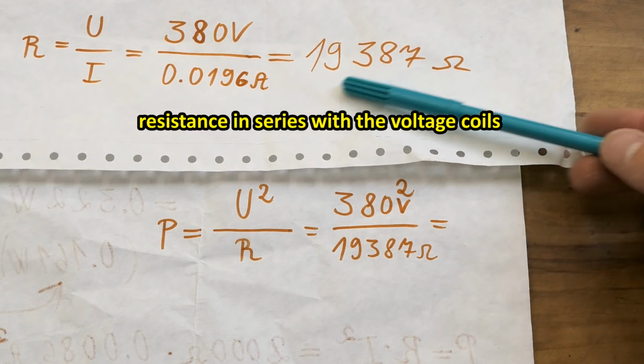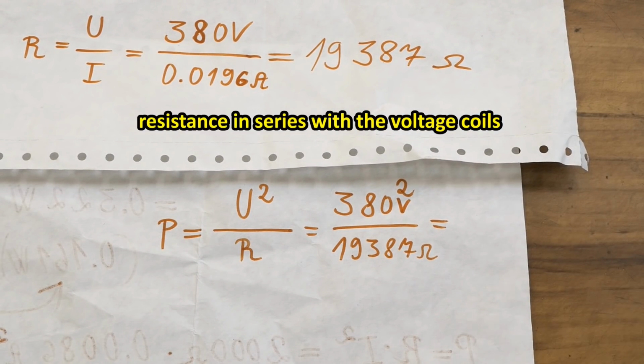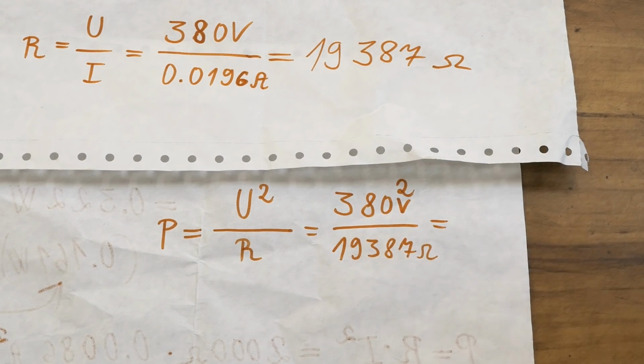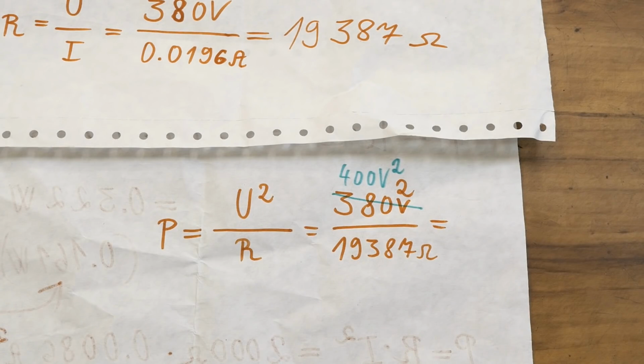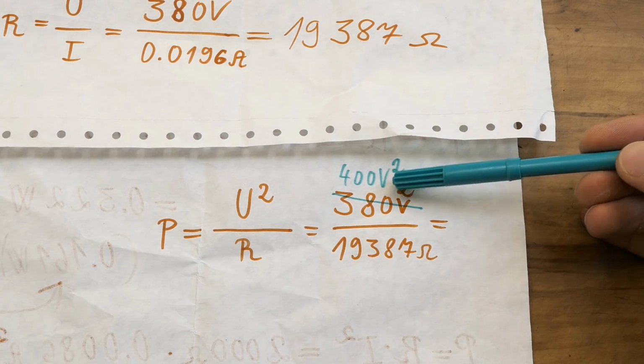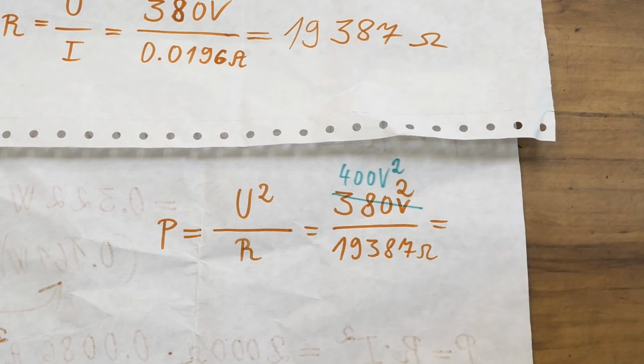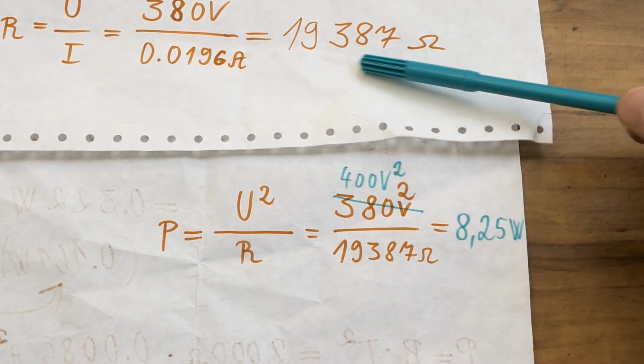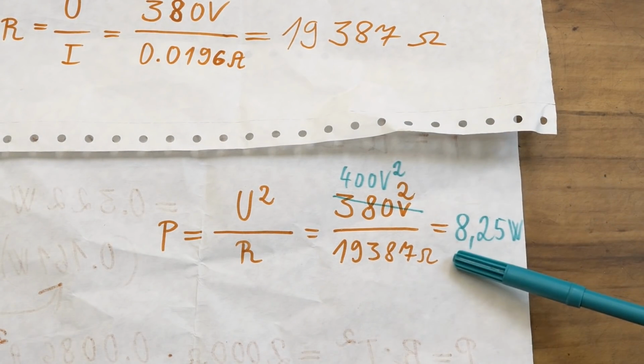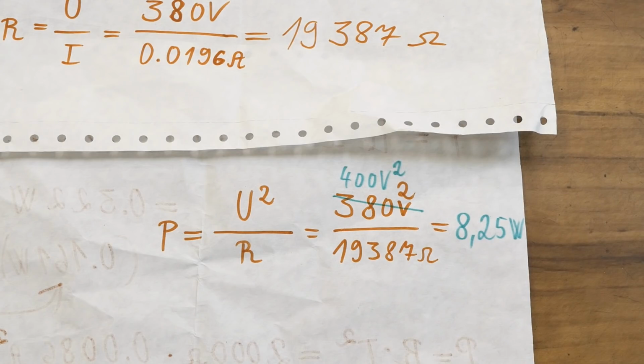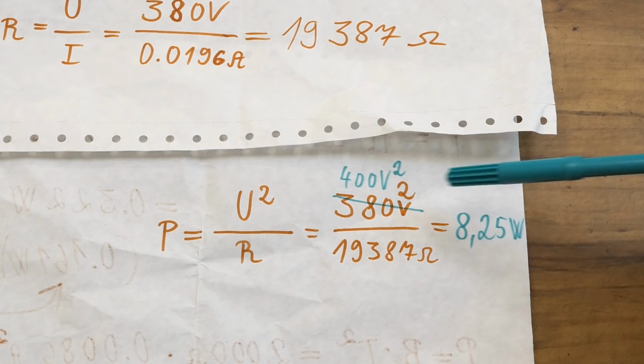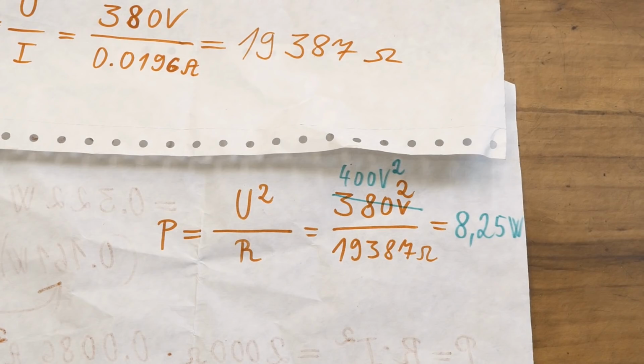So this is the lowest safe resistance I can use, but now let's try to calculate what's the power dissipation of the resistance at a certain voltage. And of course everybody's screaming that the new nominal voltage between phases is 400 volts, not 380, and the power dissipation of this resistance at this voltage is going to be 8.25 watts. So it definitely needs some power resistors, and also resistors capable of handling this voltage. But to be safe, I will use a bit higher resistance, and then the current is going to be a bit lower through the coils.